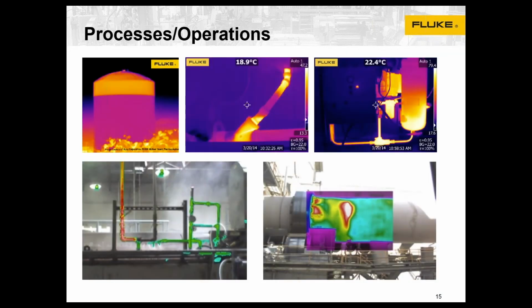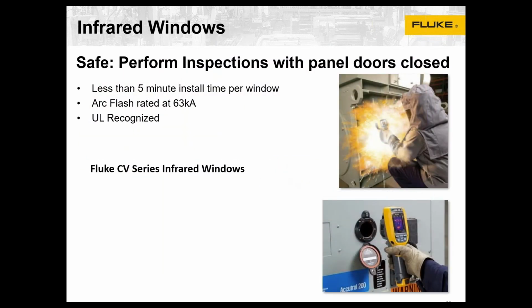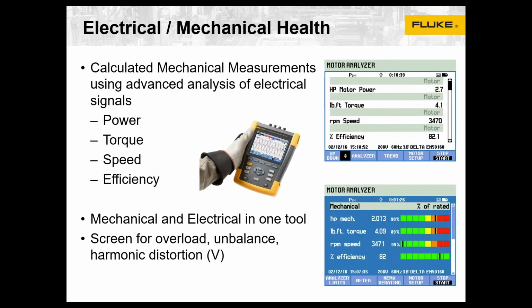And with thermography we're not going to focus on any other applications, but there is a wide variety of applications as it relates to minimizing downtime. And of course, we always advocate inspecting safely. So if you have high energy or medium voltage installations, switchgear, thermography is line of sight. We recommend that you install infrared inspection windows, which allow the infrared radiation to pass through, so you can perform inspections safely in those high energy environments. We'll take a look at a few different electrical measurements. Certainly all assets require adequate power.